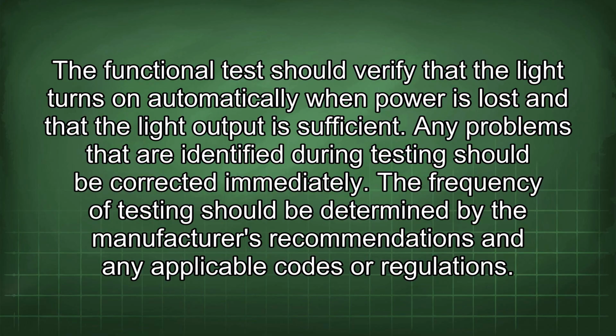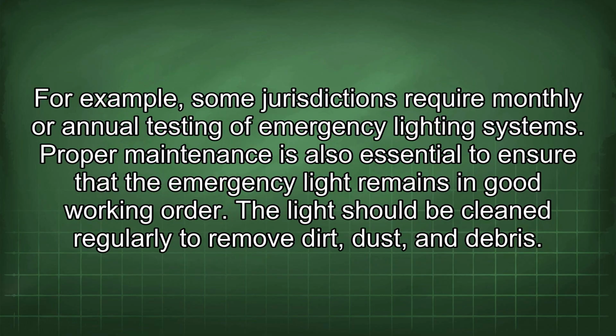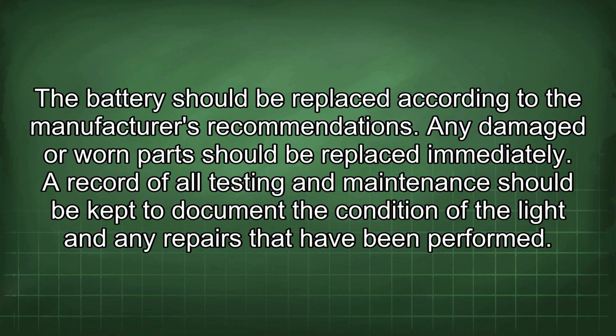The frequency of testing should be determined by the manufacturer's recommendations and any applicable codes or regulations. For example, some jurisdictions require monthly or annual testing of emergency lighting systems. Proper maintenance is also essential to ensure that the emergency light remains in good working order. The light should be cleaned regularly to remove dirt, dust, and debris. The battery should be replaced according to the manufacturer's recommendations. Any damaged or worn part should be replaced immediately. A record of all testing and maintenance should be kept to document the condition of the light and any repairs that have been performed.